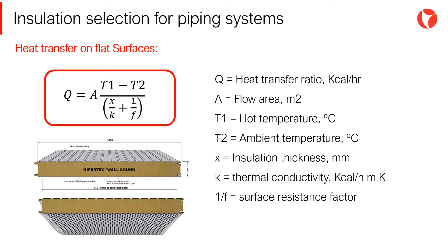For flat surfaces, the heat transfer from the surface to the environment can be expressed as shown on the screen. Where Q is the heat transfer rate, A is the flow area, T1 is the hot temperature, T2 is the ambient temperature, X is the insulation thickness, K is the thermal conductivity, and 1/F is the surface resistance factor. It can be concluded that the greater the thickness of the insulation, the lower the heat transfer rate — in other words, the greater the thickness, the more efficient the insulation.